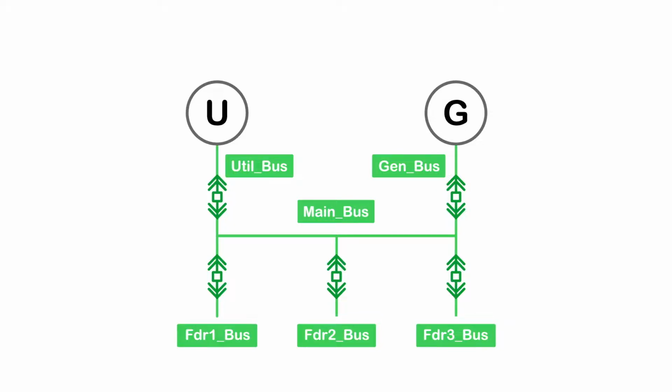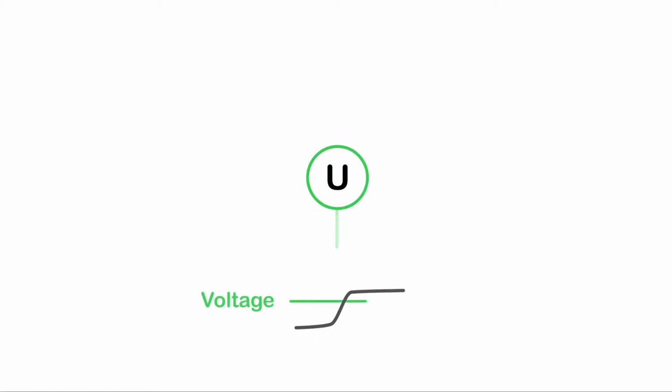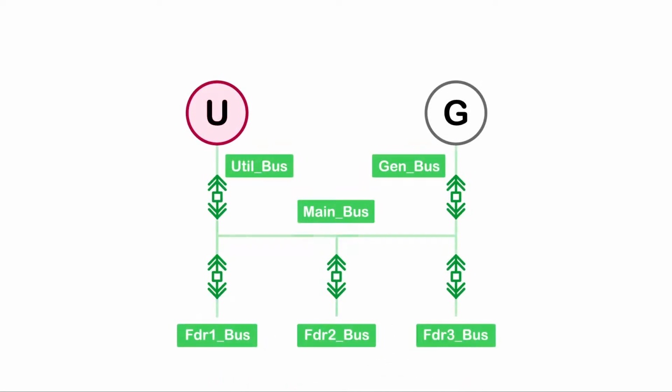Next, we have sources of energy. A source has an active condition driving it. When this Boolean condition is true, the source will energize the bus with its configured color. Ideally, this active condition will be a fixed indicator, like an undervoltage relay is off or a generator is running. However, we can also trigger on analog conditions, such as voltage being over a certain level. In either case, the source is what sets the color of the bus it is attached to.